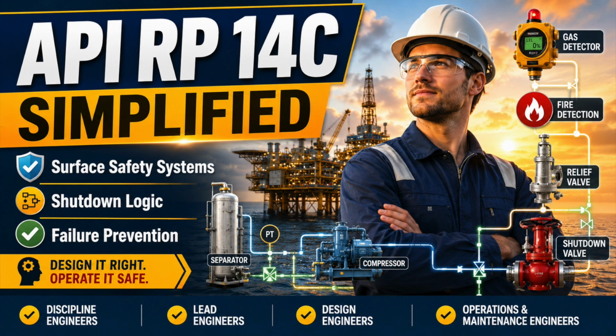The main hazard is not pressure, level, temperature, or flow by themselves, because those are process variables. The real hazard is the chain that begins with an abnormal condition, develops into equipment failure or loss of containment, releases hydrocarbons, exposes people and equipment, finds an ignition source, and escalates into fire, explosion, pollution, or platform-wide shutdown. Your safety system must interrupt that chain at several points.